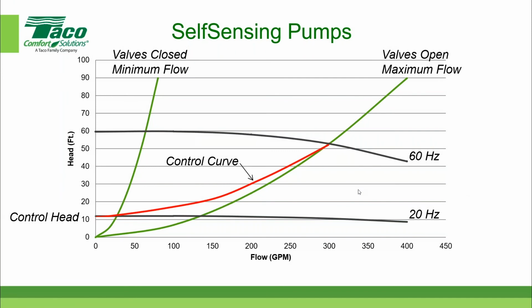Okay, so again, the control curve represents where the computer is asking the pump to operate between its maximum speed and valve open position to its minimum speed and valve closed position, with the exception of three-way valve. And the computer is going to force the pump to stay on this red line, which emulates what a differential pressure transmitter does in a conventional control system. So this, in a nutshell, is how the self-sensing pump functions. It controls the speed of the pump; the self-sensing variable frequency drive with its computer and its software forces the pump to stay on this red line.